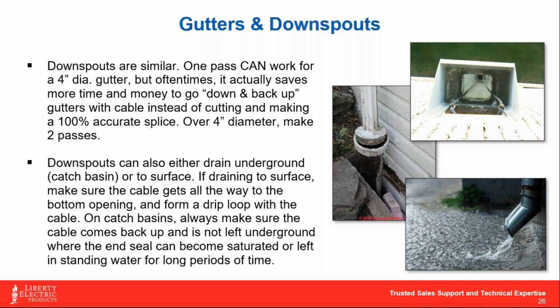You just try to get the cable pulled down about 2 to 3 feet underground, which gets you below the frost line. One tip I give installers is to drill a small weep hole in the back side of the downspout, so if the cable doesn't get down far enough and water starts to freeze and work its way back up, it has a way to exit before it pressurizes and goes all the way back up to your roof.